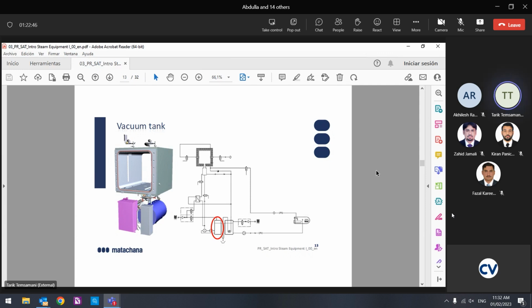The consumption, you know the consumption by cycle? 200 liters? It depends on the type of chamber. If we talk about the S500, we talk about 250 liters by cycle. And what about the RO water? What is the consumption by cycle? 20, 25 liters by cycle. Very little in comparison with the soft water. Okay.